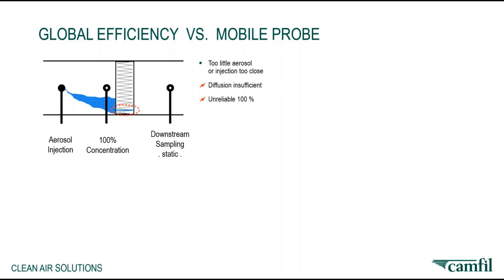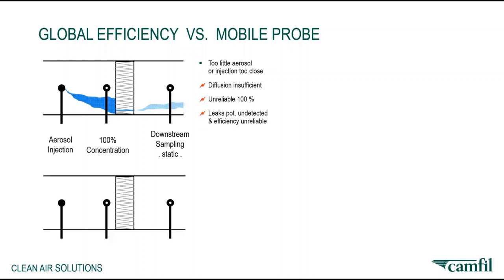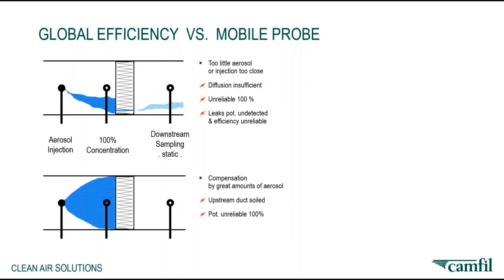And if you have a little leak stream somewhere on the side, this is, again, a different issue. And even a little leak stream might be too much for a H13, H14 filter. Depending on the position of this leak stream and the position of your static probe, you just might not get it. Typical compensation attempts involve great amounts of aerosol. But the only thing you achieve by that is getting your upstream duct wet. Only thing is, full coverage, it looks really nice here, does not mean a good distribution. So once again, your 100% might still be unreliable. And the same goes for your leak stream. As I said, it's an independent problem. And even if you're using a shaped probe to cover more points in the airstream, you'll only get a better chance, not a guarantee.